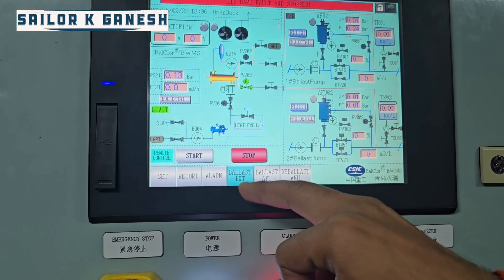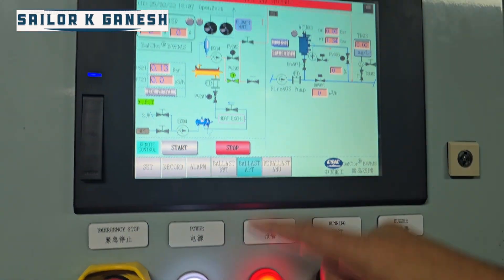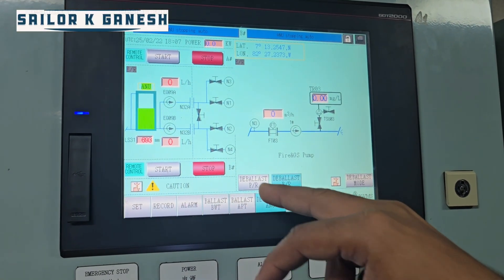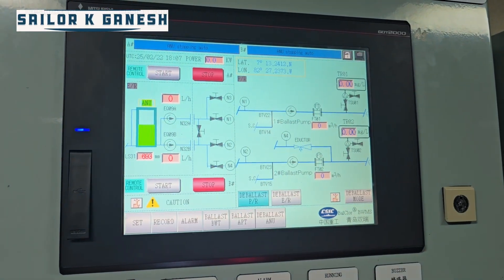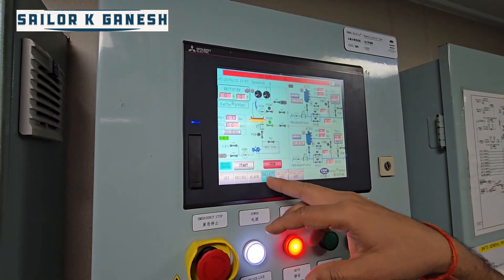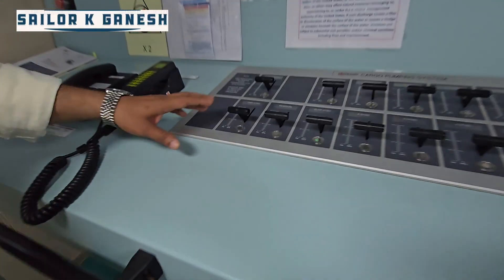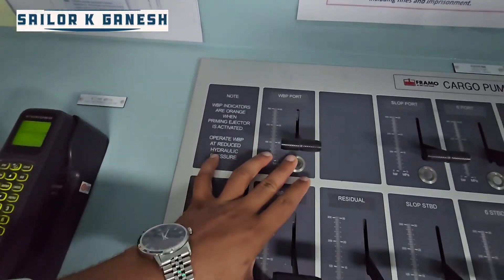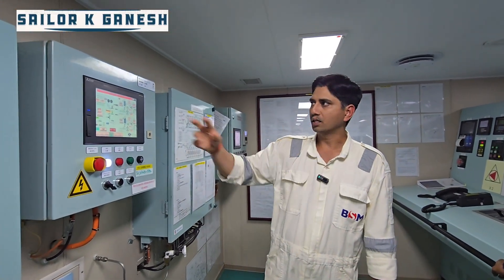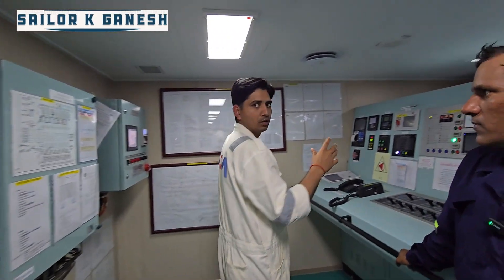When you need to take ballast, click on the ballast BWT option. When you need to de-ballast, select that option. There are also two options: for engine room and for pump room — pump room means the deck side. When starting the ballast system, go to this mode, start it here first, and then start the pumps. Two pumps with capacity of 1,000 cubic meters per hour each — ballast pump 1 and ballast pump 2. Before starting, make sure the ballast system is started and the blowers are on in the EDU blowers as well as the BWTS room blower.